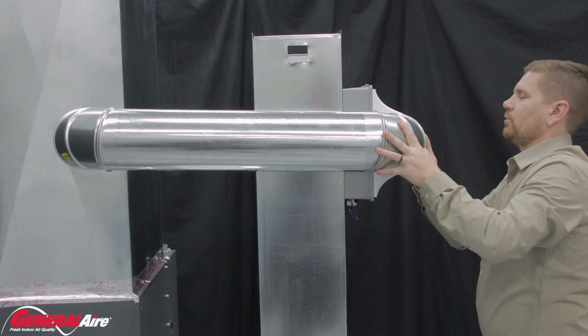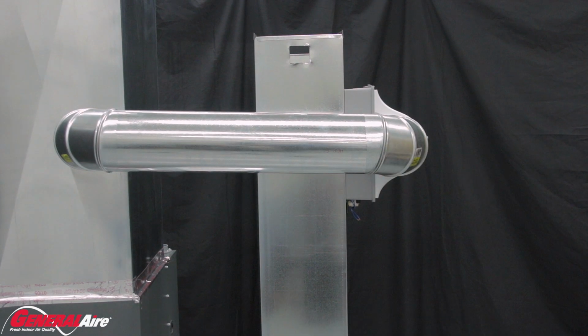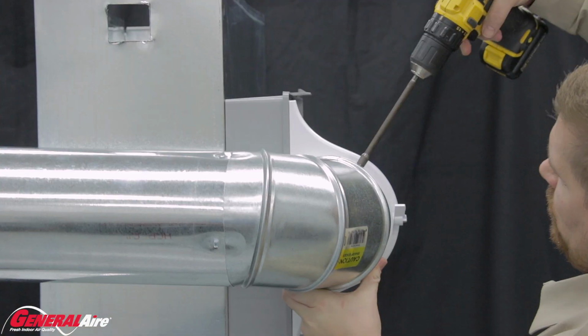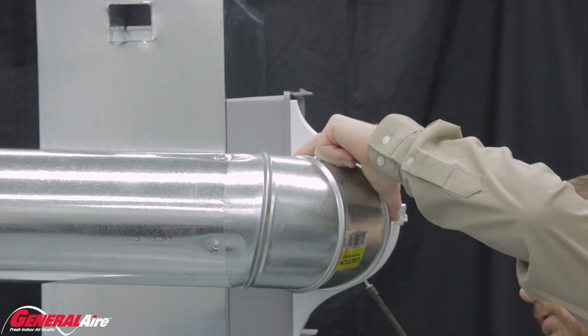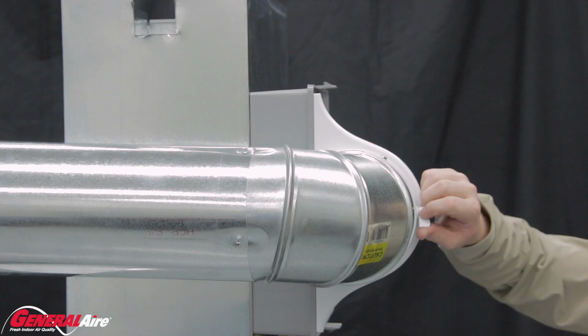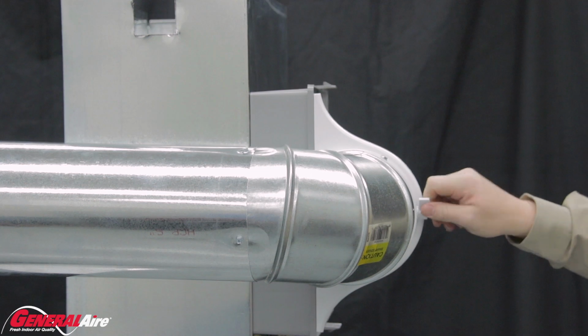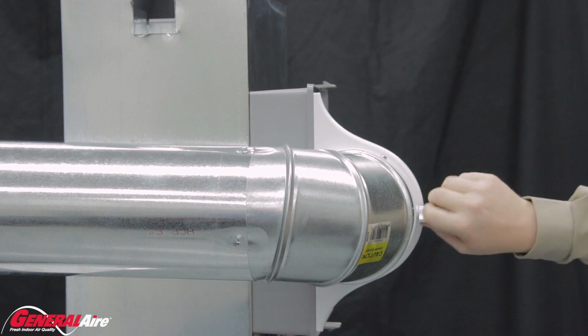Cut the round sheet metal to that measurement using the tin snips. The finished bypass should connect the side of the humidifier to the opposite ductwork via the 6-inch round pipe and, if needed, elbows. Secure the joints of the ductwork together with sheet metal screws, using screws less than 1 inch long on the bypass at the humidifier to ensure the bypass turns freely.